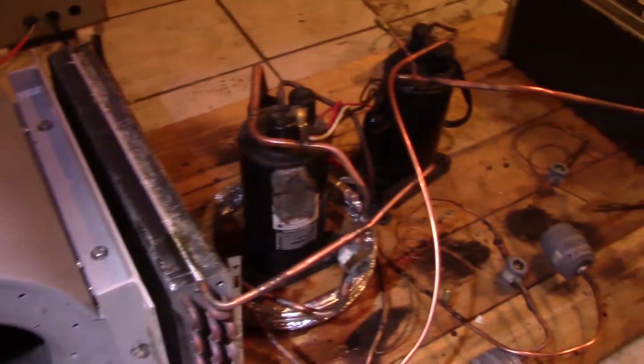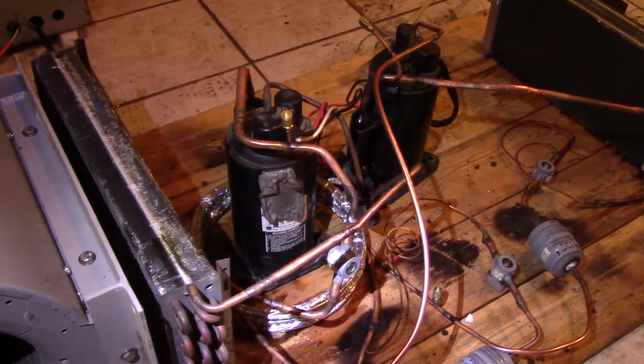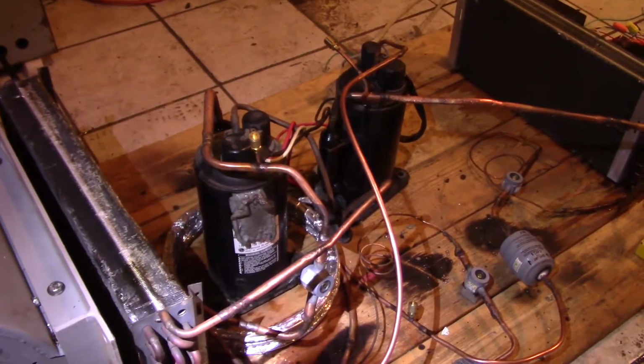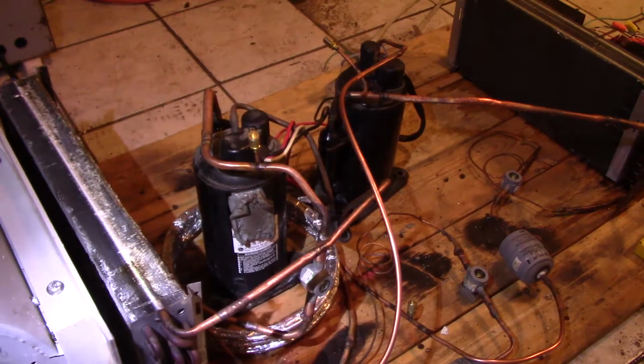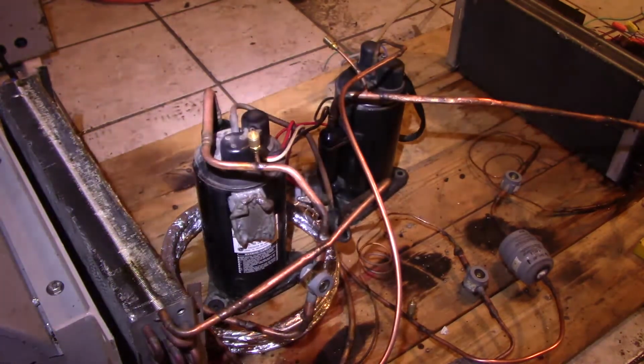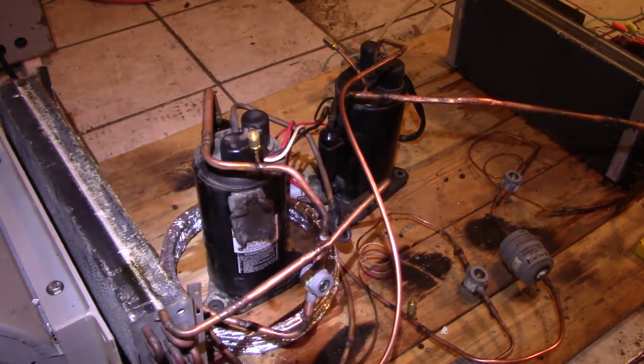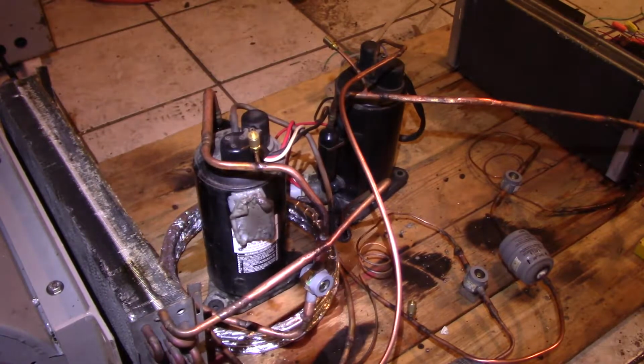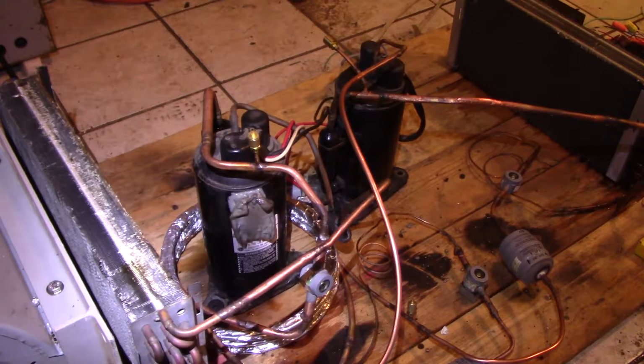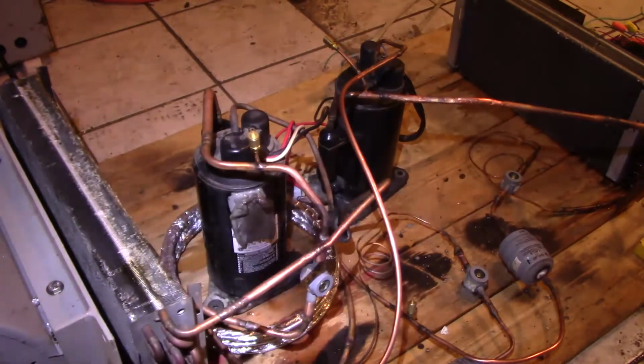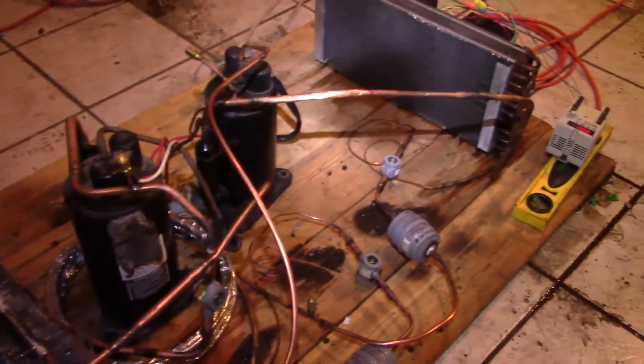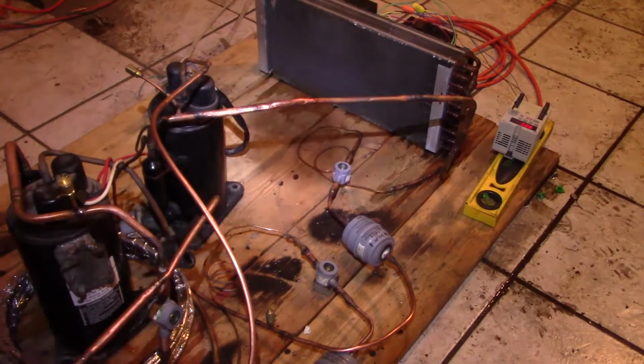Now this whole system here uses R404A for both cycles. These 2 compressors came out of 2 window air conditioners. The lower temperature cycle compressor, the one on the right, is rated, I think, 8,000 BTUs an hour, and the one on the left, which is the high temperature cycle compressor, is rated 9,000 BTUs an hour. So yeah, that evaporator over there is not meant to handle all this power.